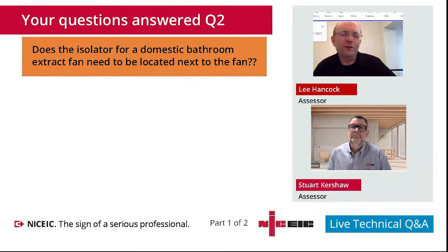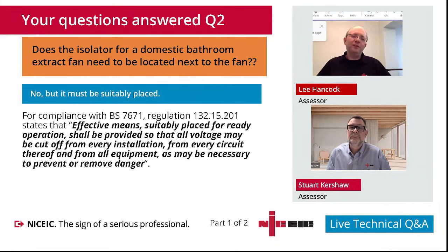No, it doesn't, Sam. Ultimately, if we're dealing in a bathroom situation, the isolator needs to be external, ideally. 132.15.201 is going to give us a little bit of additional support on this. If we look historically on new builds, fan isolators used to be located above bathroom doorways, just as a means of isolation, not switching. Ultimately, if a fault develops on the fan and we need to isolate it, we can't access that switch. You may find people are going to be using their MCB, their consumer unit, which could lead to a further issue, because you could be putting the place into darkness.